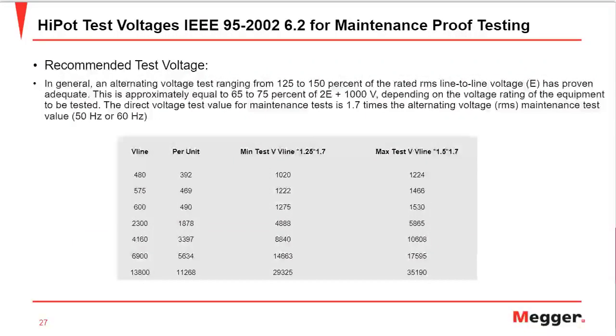There are various standards. The first one is IEEE 95. The latest version was 2002. This standard helps us calculate the test voltage with the rated voltage of the motor as a reference. For example, for a 480 volt motor, the minimum test voltage we would use is 1020, calculated by a factor of 1.7. And the maximum is 1224. So 125% to 150%, we can use any test voltage within this range for a 480 volt motor. Similarly it goes on for different ratings of a motor.